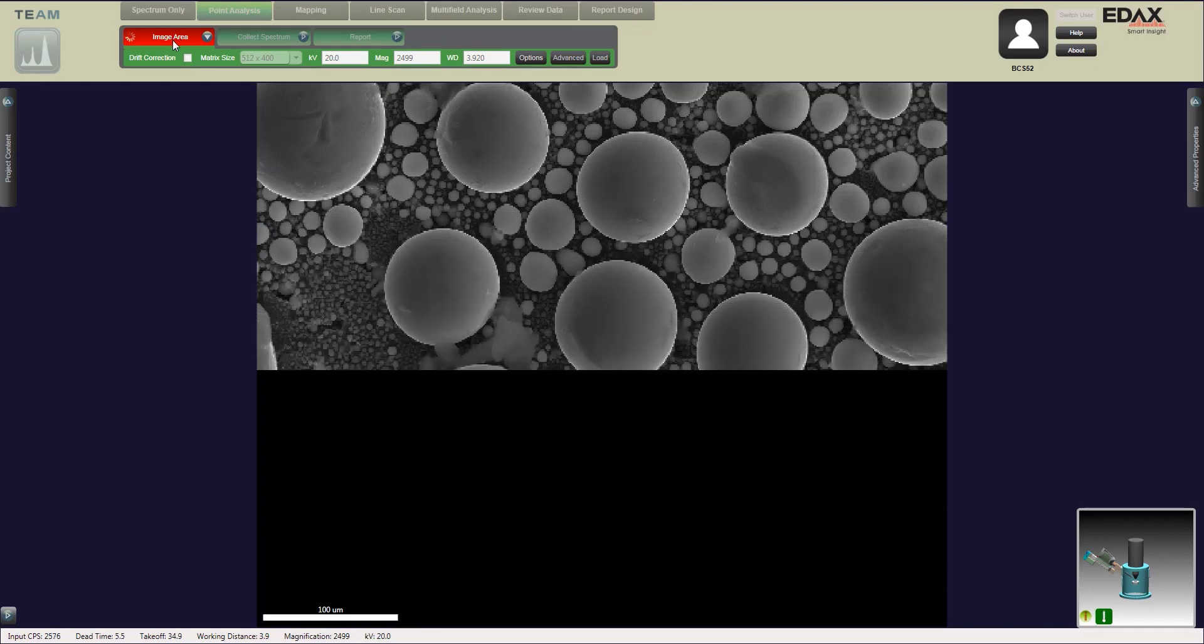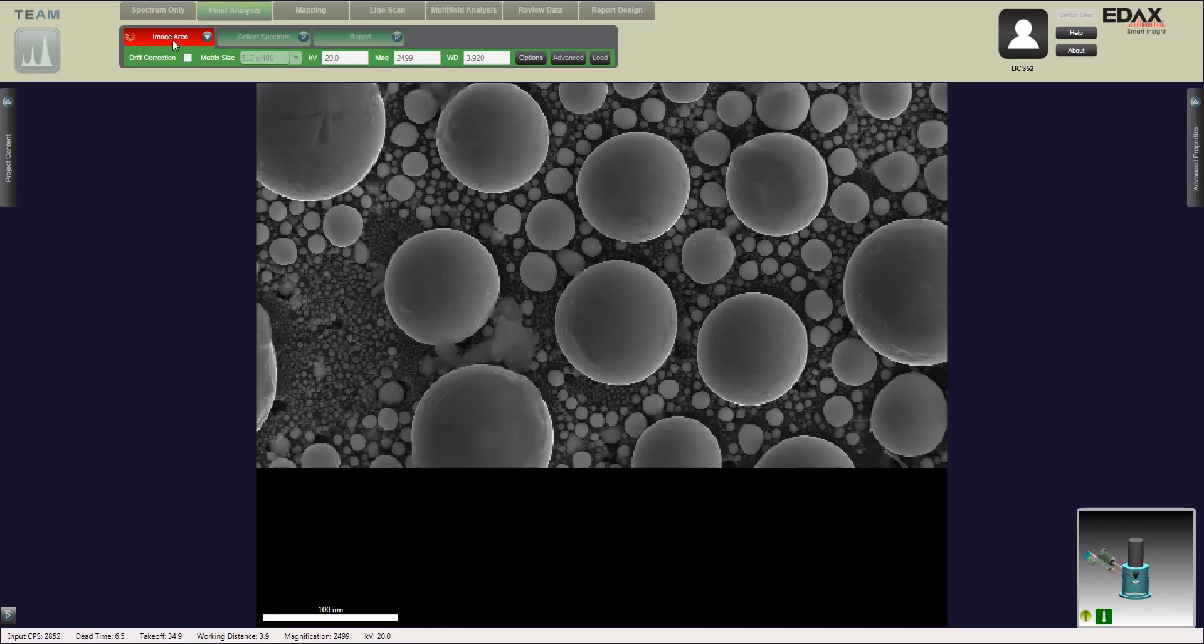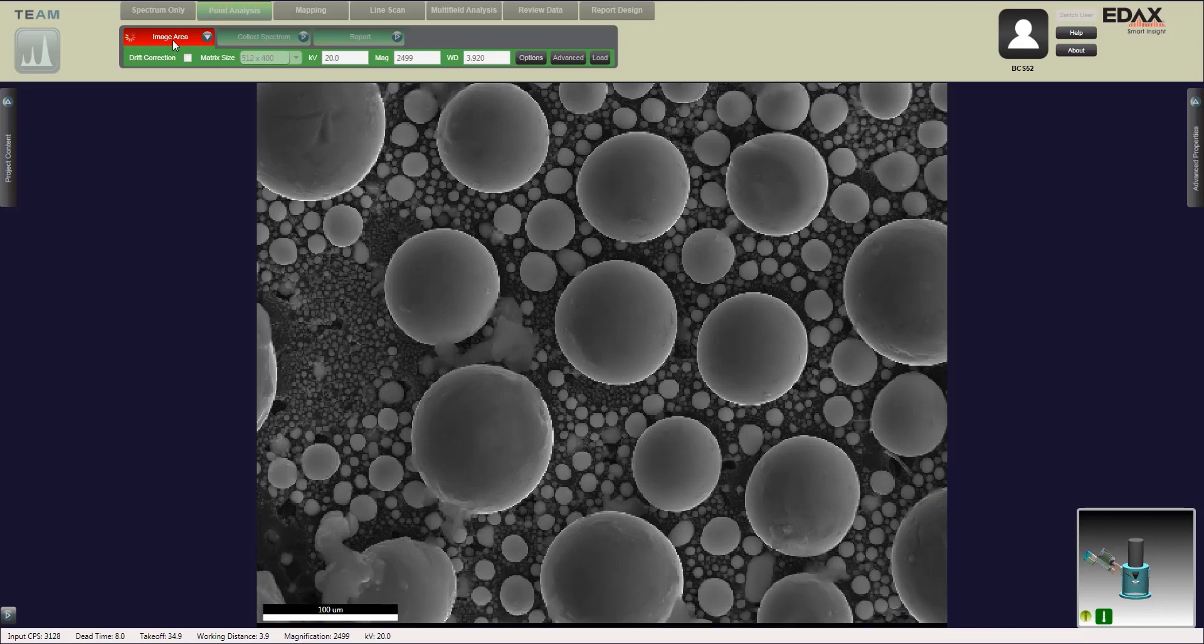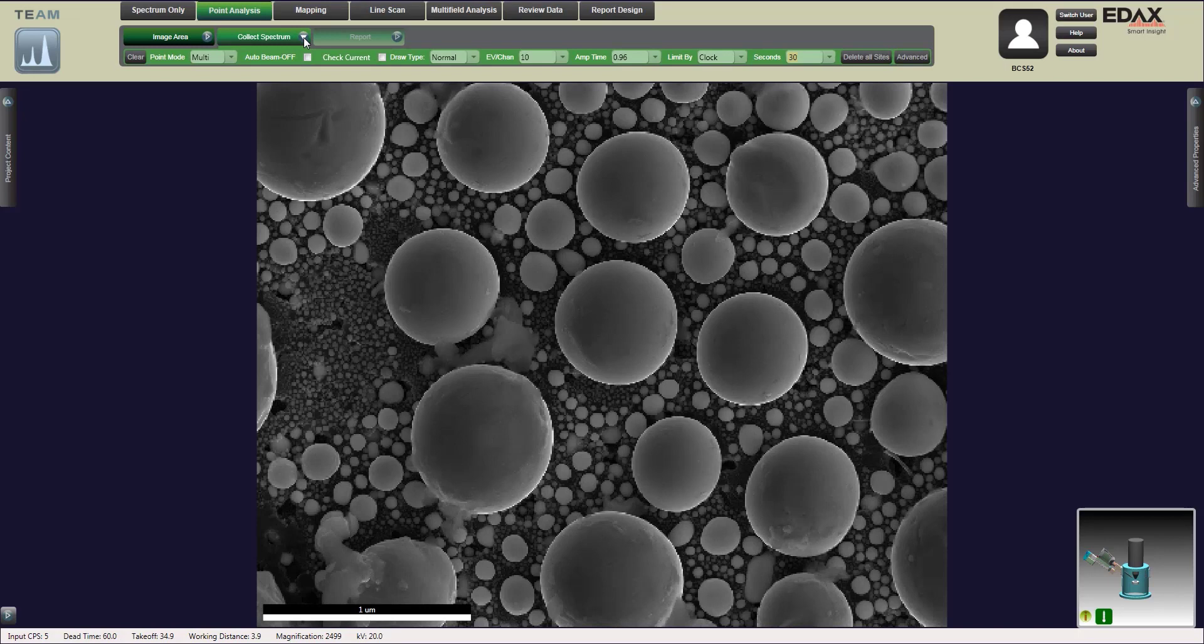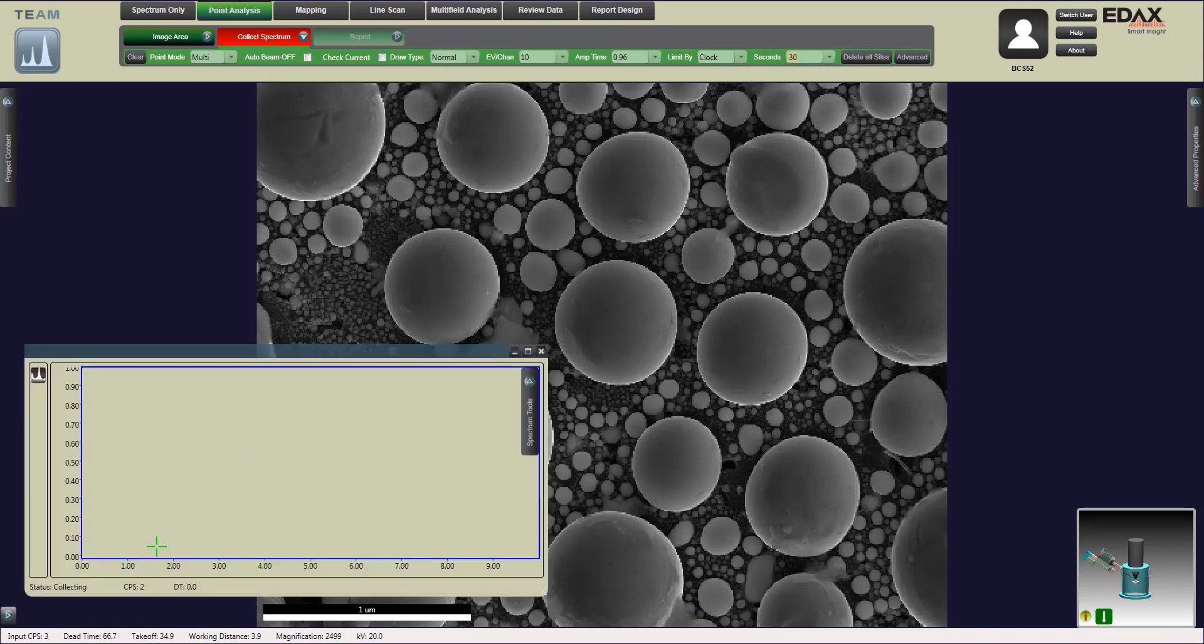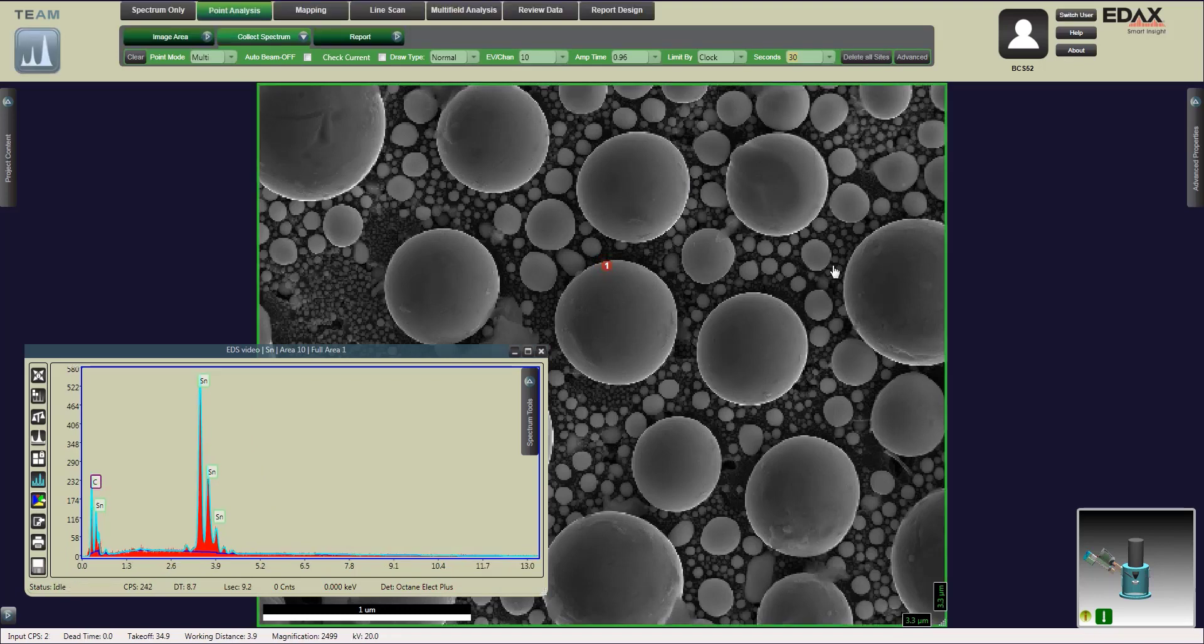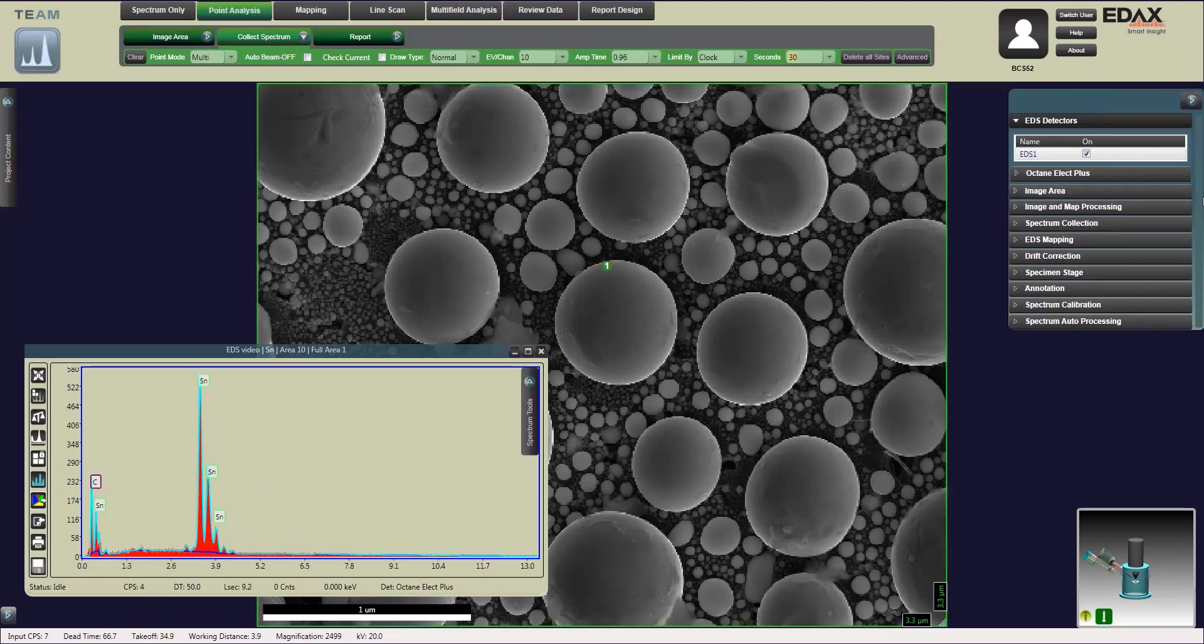Our imaging image is coming up and we can look at our input CPS around 3000. Dead time is 5.7 so we need to make some adjustments to change that. To increase our input counts per second, we need to go back to our control and increase the current. For collect spectrum we do have options to change the time and amp time. We see we're right around 3000 CPS. We can always click the collect spectrum button to stop the scan. Off screen, I'm on the other PC changing the current, increasing the current to increase the counts per second rate.